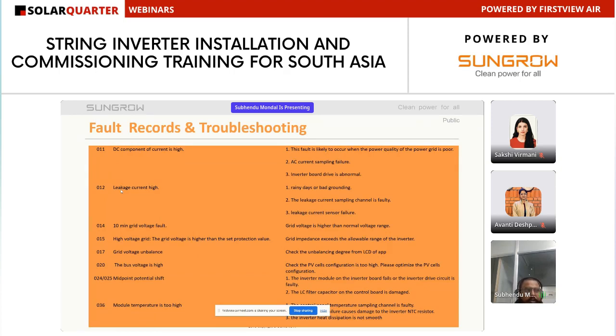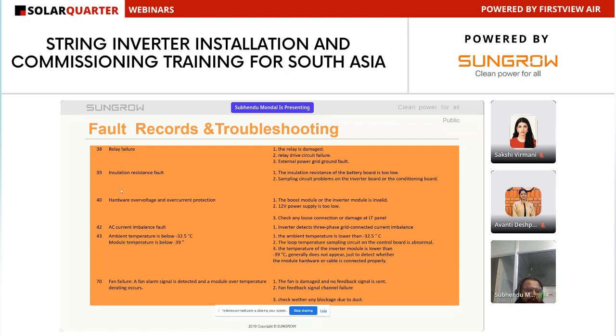24, 25 midpoint potential shift. 36 module temperature is high. It may be some damage in a capacitor, a temperature sampling channel fault, or maybe an LC filter capacitor fault or internal damage, so this will show. These are all hardware related issues. 38 is relay failure. If the relay is damaged, it will show 38. 39 is low insulation resistance. The insulation resistance of the battery board is too low, or there are sampling circuit problems on the inverter board or conditioning of the board.